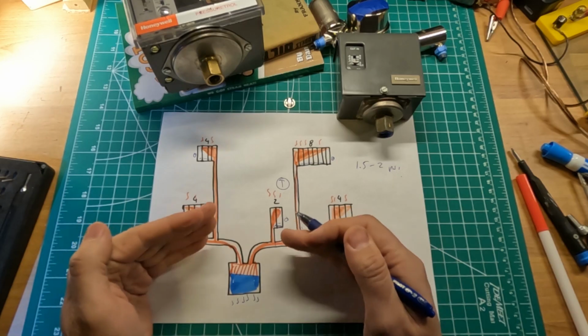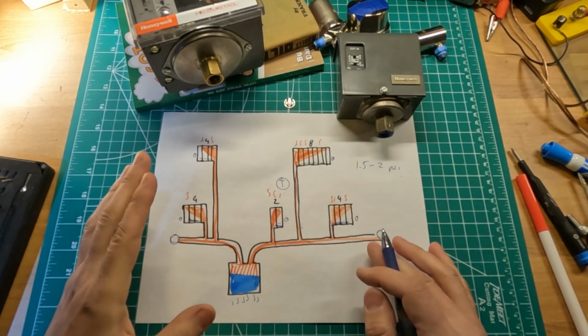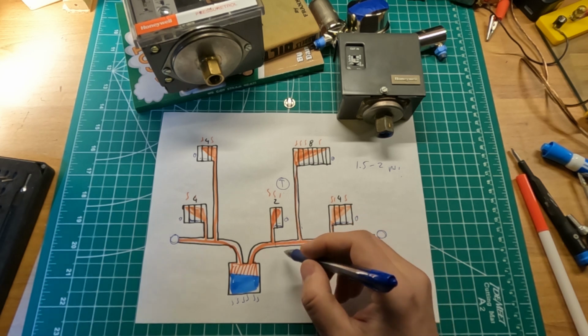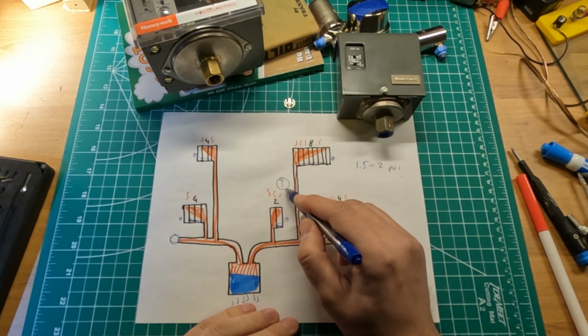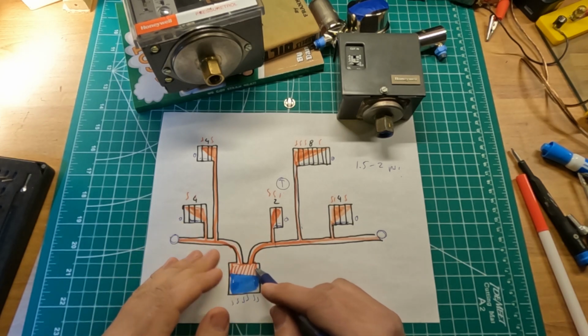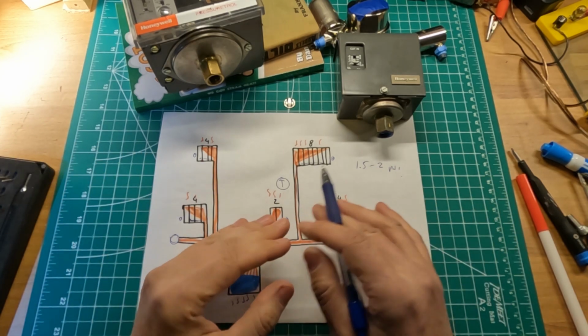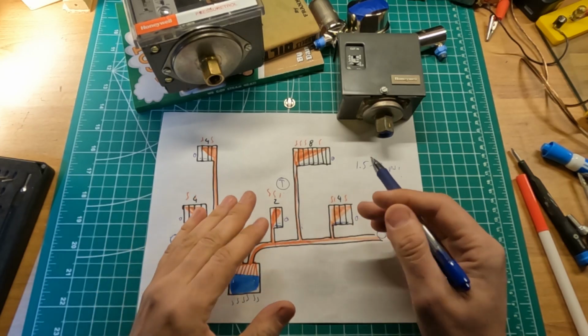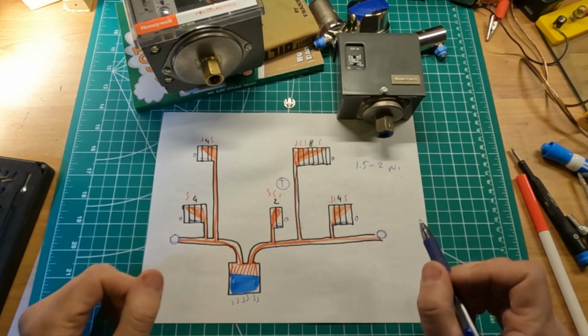So in other words, the boiler is working for no reason whatsoever. In a perfectly balanced system, the moment the radiators give off enough heat to satisfy the thermostat, the boiler shuts down, and there's no buildup of pressure whatsoever. Again, maybe just a tiny amount of poundage, let's say a quarter of a psi.